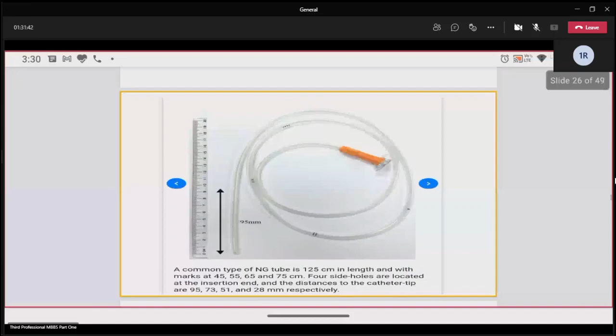4 side holes are seen. See here in the picture, you are able to see the 4 side holes. The distance from the tip to the holes is also given. The first one is 28 mm, meaning 2.8 centimeter. The next ones are 51 mm, 73 mm, 95 mm. Another slide is showing how to measure the length of the nasogastric tube which is required.